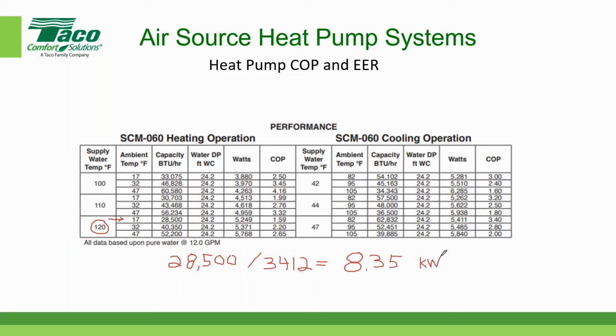Alicia did. Okay, and I'm going to make this a shortcut here. So that's this 28,500 divided by 3412 BTUs per kilowatt hour. And then I divide this number by 5,249 watts. Since the units are watts, I know if I divide the watts by 1,000, 5,249 would be 5.249, right? Yep. And that's also in the units of kW.